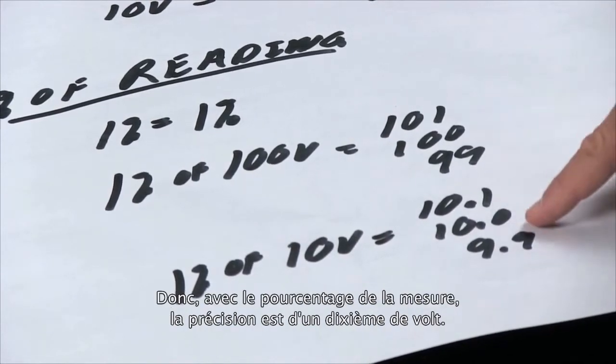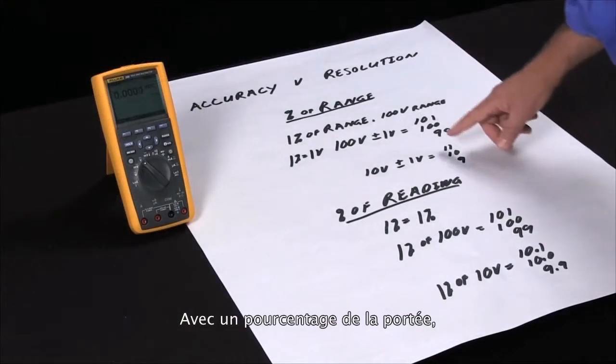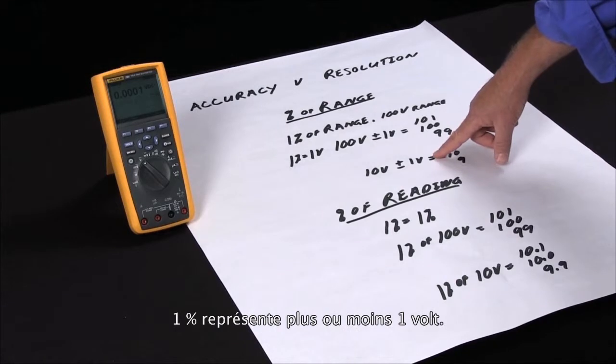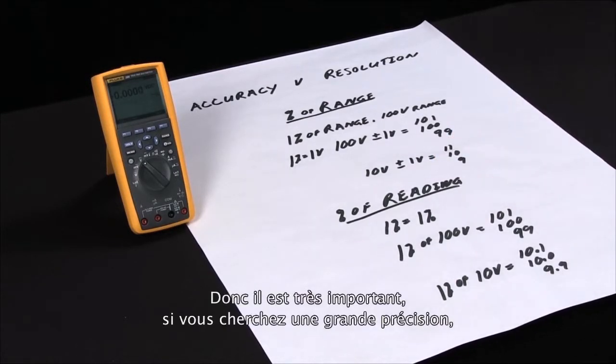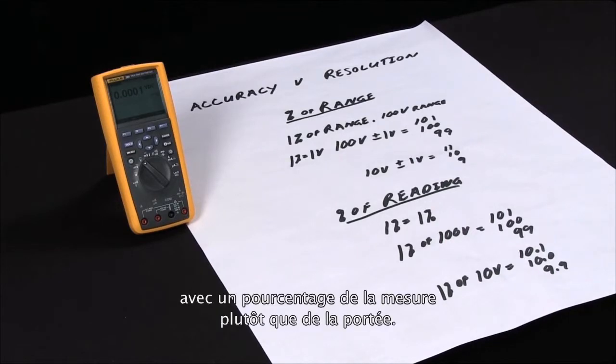So here with percent of reading, the accuracy is a tenth of a volt. The same thing specified with percent of range, one percent is now plus or minus one volt. So it's very important if you're looking for accurate readings to make sure you select a device with a percent of reading versus a percent of range.